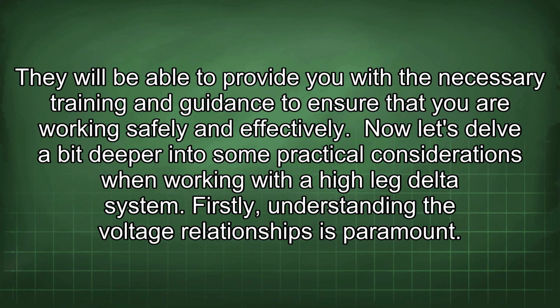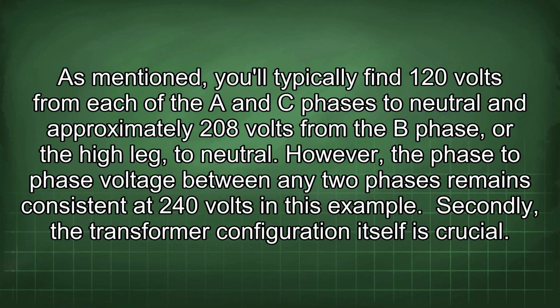Now let's delve a bit deeper into some practical considerations when working with a high leg delta system. Firstly, understanding the voltage relationships is paramount. As mentioned, you'll typically find 120 volts from each of the A and C phases to neutral and approximately 208 volts from the B phase, or the high leg, to neutral. However, the phase-to-phase voltage between any two phases remains consistent at 240 volts in this example.